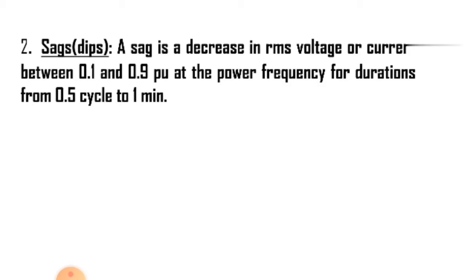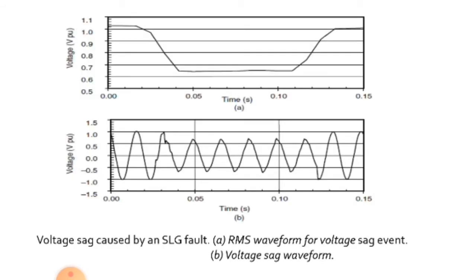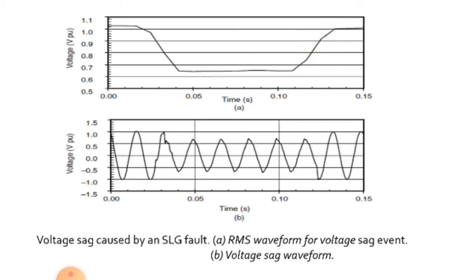Then coming to sags, also called dips. It is a decrease in RMS voltage or current between 0.1 and 0.9 per unit at the power frequency for a duration from 0.5 cycle to 1 minute. Voltage sags are usually associated with system faults but can also be caused by energization of heavy loads or starting of large motors. This graph clearly shows a typical voltage sag associated with a single line to ground fault on another feeder from the same substation. An 80% sag exists for about three cycles until the substation breaker is able to interrupt the fault current. Typical fault clearing times range from 3 to 30 cycles depending on the fault current magnitude and the type of over-current protection.